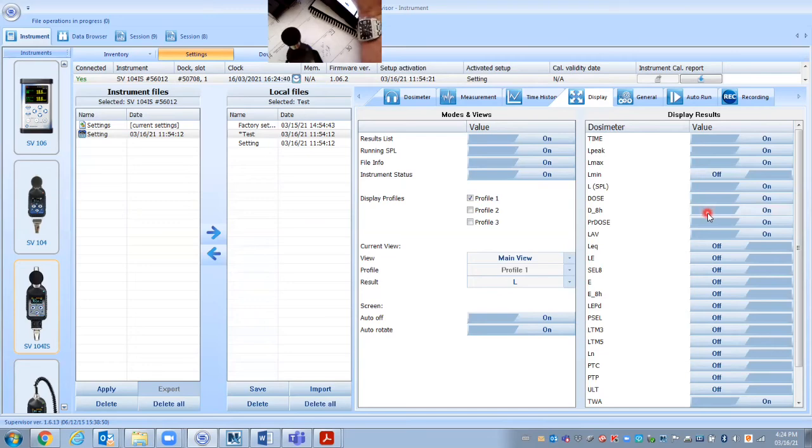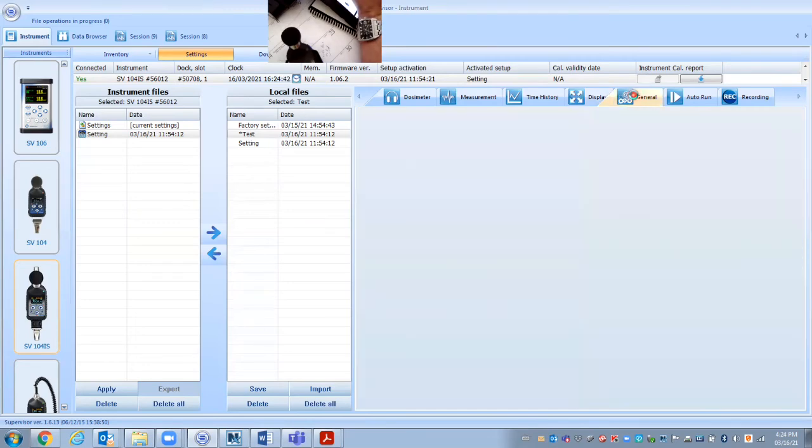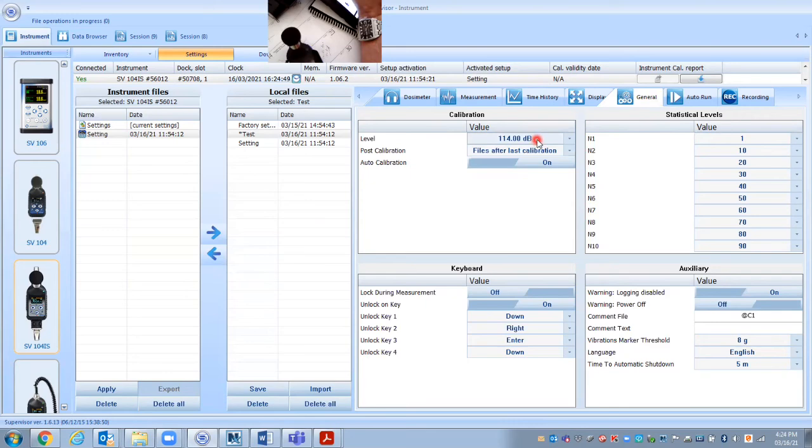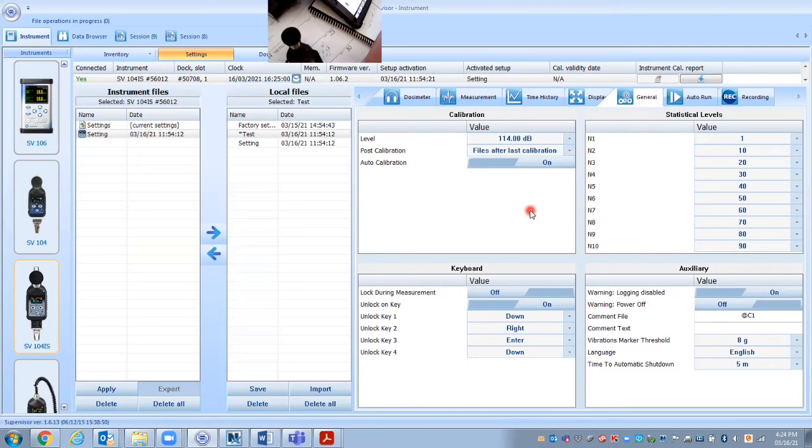We may or may not want to even look at them on there. We may want to just download the results. So under general tab, under calibration, the calibrator that comes with the dosimeter, there's two different, there's a dual frequency calibrator or single and standard one is 114 dB. So we want to make sure that's set for it. These other things we're not going to get into.